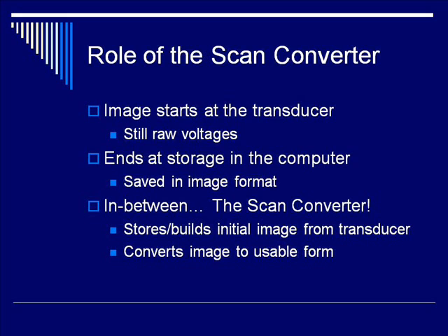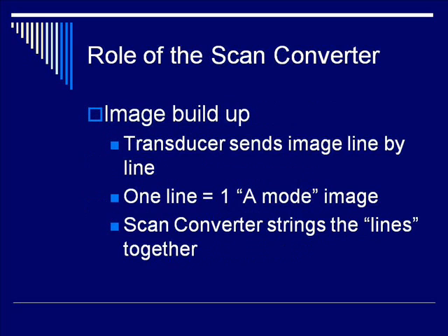The scan converter has two main roles. It stores and builds the initial image from the transducer, and then it converts that image to a more usable form. Recall that we essentially create a B-mode image by stringing together a series of A-mode images. Any given line in your B-mode image could be described as a series of varying voltages, which is what an A-mode image is. The scan converter converts these voltages into numbers, and then converts those numbers into an image.